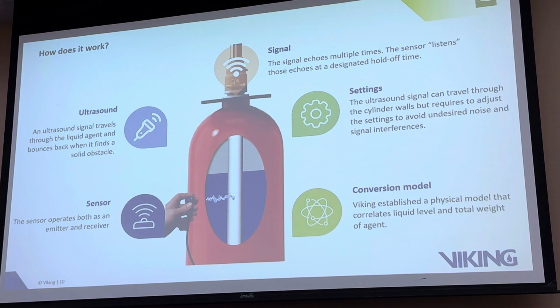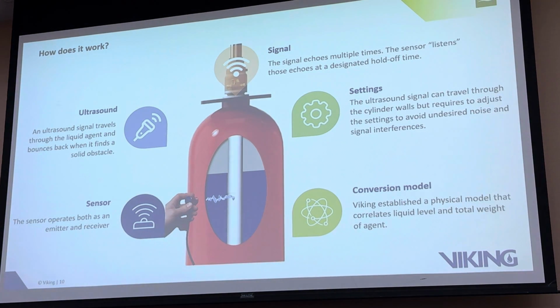When we have the level, what matters is the agent amount. In the manual there are conversion tables that tell you, for this cylinder at this pressure and this temperature, this is the level, this is the number of kilograms. The conversion depends on several factors that decide the accuracy: pressure, the internal volume, the type of agent, the solubility of nitrogen, and a lot of thermodynamics. So it's not enough to know the level, you need to know the agent content, and you find that in the manual.